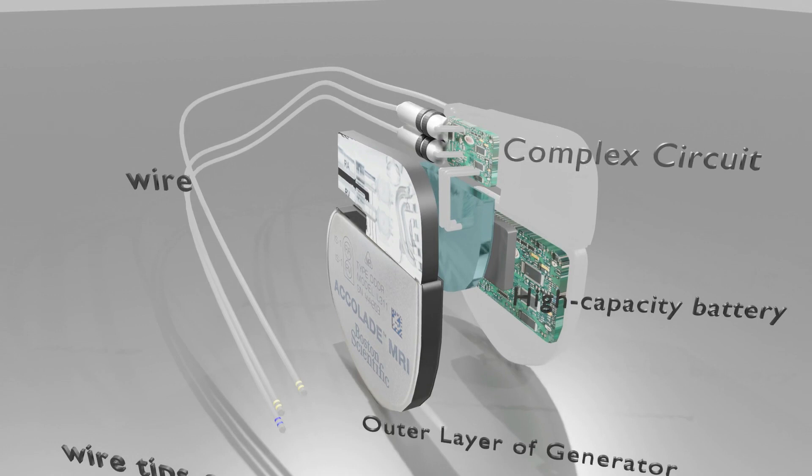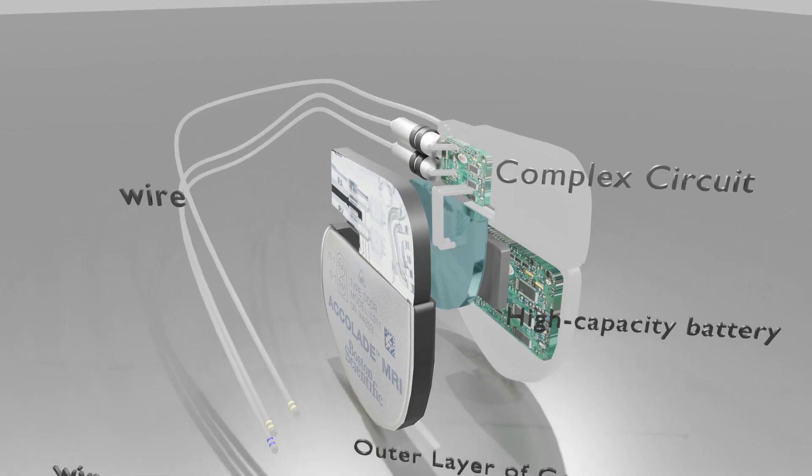The third component is the battery. Each ICD has a battery whose lifetime is dependent on how much pacing and defibrillating the device is called upon to perform. Typical longevities fall between about four to seven years.